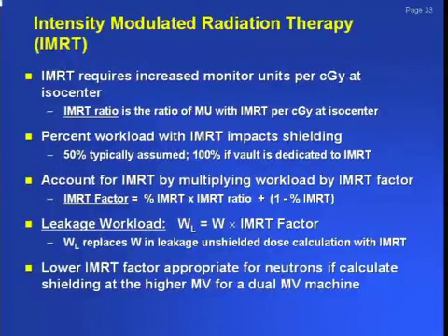Varian and Elekta both now say it is down to about 2.5 with VMAT or RapidArc. So typically your monitor units are about 2.5. We are using 3, but that is the factor I would recommend. I think Siemens is still running about 5, but that is a number that would need to be checked with Siemens. But I know Varian and Elekta both run around 2.5 to 3 for your IMRT factor.